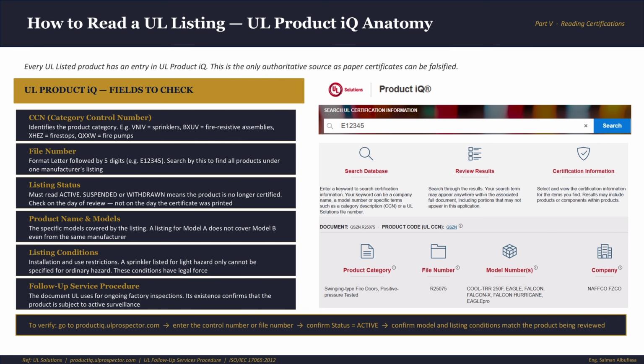Go to UL Product iQ, enter the file number or model number. Confirm the status is active, confirm the model matches exactly, confirm the listing conditions match what is being installed. That's it. And everything we mentioned, you can see it on the right side: the product category, the file number, the model number, and the company itself. And in the next slide, I will show you exactly how to do this live.